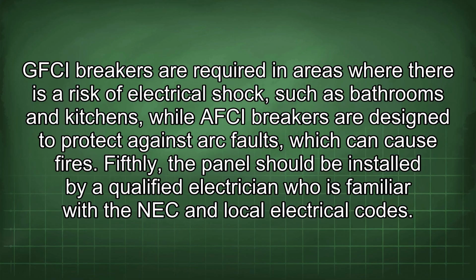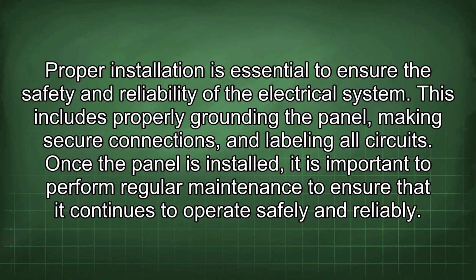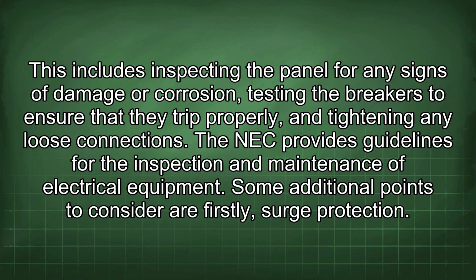Fifthly, the panel should be installed by a qualified electrician who is familiar with the NEC and local electrical codes. Proper installation is essential to ensure the safety and reliability of the electrical system. This includes properly grounding the panel, making secure connections, and labeling all circuits. Once the panel is installed, it is important to perform regular maintenance to ensure that it continues to operate safely and reliably. This includes inspecting the panel for any signs of damage or corrosion, testing the breakers to ensure that they trip properly, and tightening any loose connections. The NEC provides guidelines for the inspection and maintenance of electrical equipment.